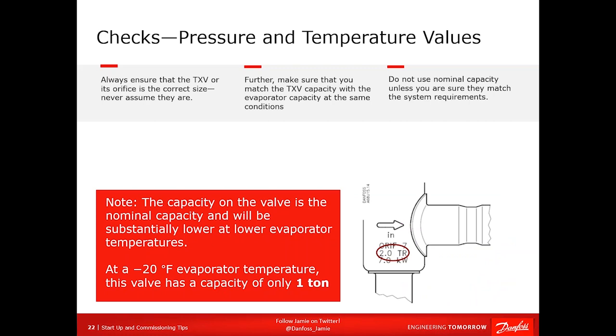Another fun one that comes up quite a bit. You will notice if you look at a TXV in a catalog, it will say 1 ton or 2 tons or 5 tons or whatever. And that's fine if you're running air conditioning, because what that tells you is the nominal capacity of the metering device. And nominal capacity is done at 45 degrees or 40 degrees, which is pretty much AC temperatures. So you're good to go.